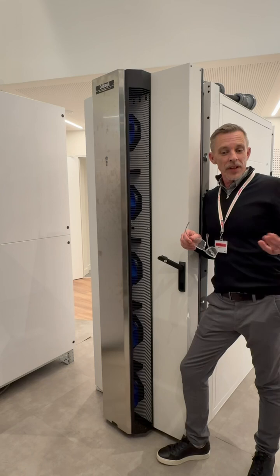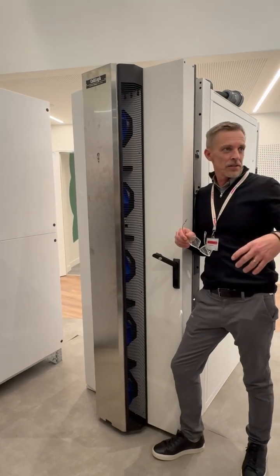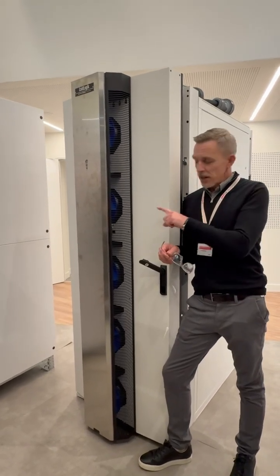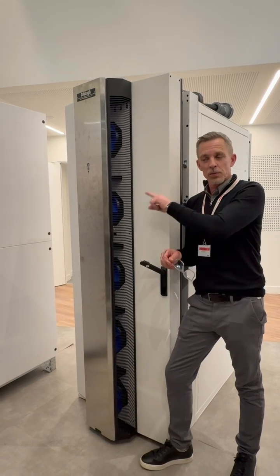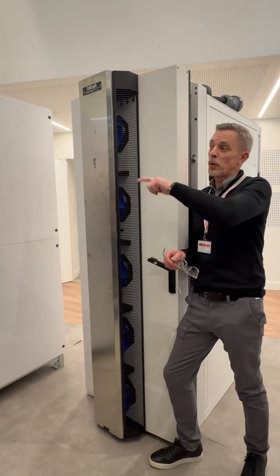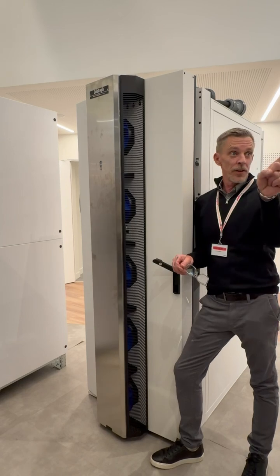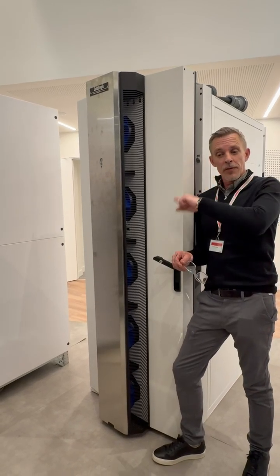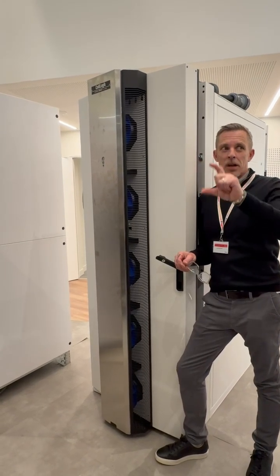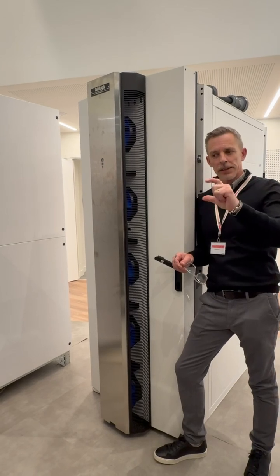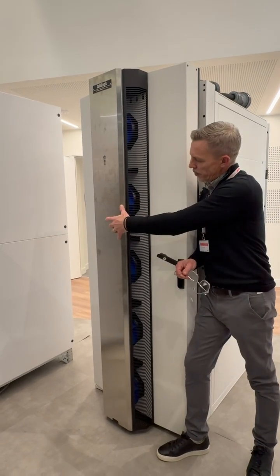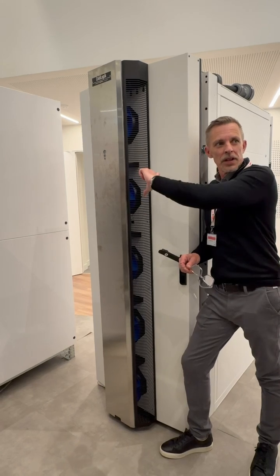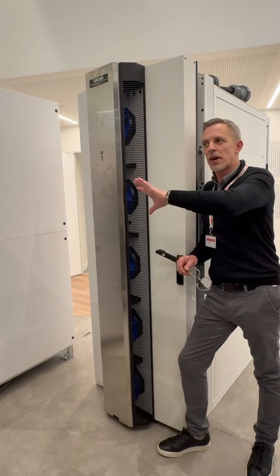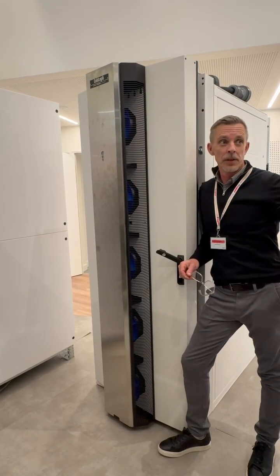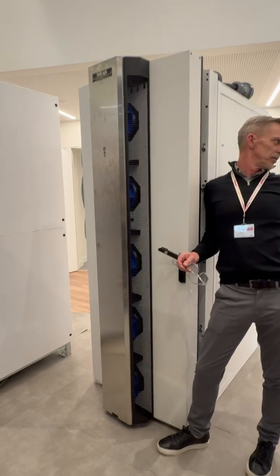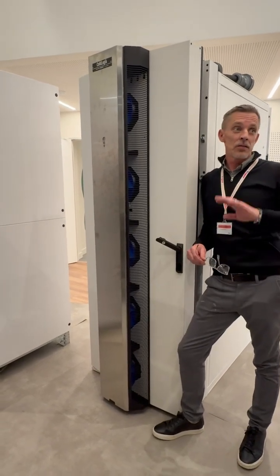So, like anything, they're on bearings. Bearings after a period of time wear down. Nice thing about these is they're hot swappable. So what this will do is it will connect back on a building management system, direct feed to their system, and if it fails, it will show on there that the fan is slowing the capacity, not failed, slowing. So the engineers can come out, pop this panel off, there's 4 screws, they remove the fan and plug it back in while still active. So there's no downtime. We've had it where we've had all fans fail. Again, the engineers will come in and just replace it.